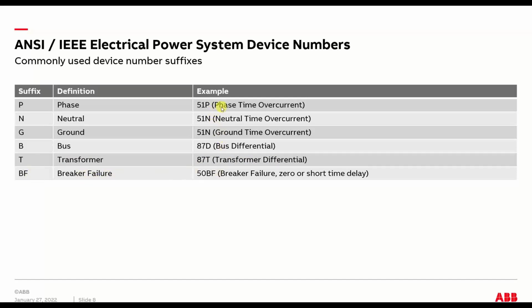And usually when we get into the numerical relays, these are going to be important because each element in the numerical relay will say that it's a 51P or a 51N. And that terminology even shows up within EasyPower itself when you select a specific relay. You know, it might be ABB REF 615, and the actual library is for the neutral protection, so it'd be a 51N. So these are the important ones to know.